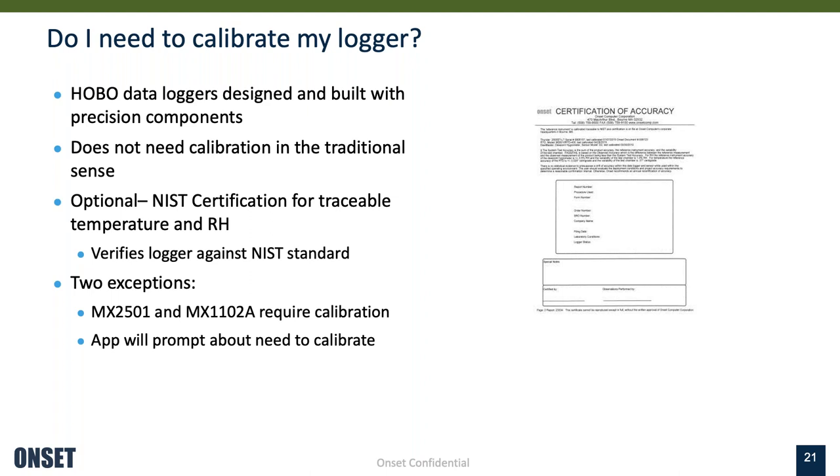And there's two processes there. One is a manual calibration where you would configure that device, and during that process, you're going to go through the actual calibration. And we recommend in that case, with the CO2 logger, you do that outside, right? So you want to get to a position where you're at the lowest CO2 that you can be for that calibration. Then there's also an AutoCal setting that you can run, and I believe it's every week or every 8 days it goes through this AutoCal process where it will do a little bit of math and auto-calibrate at that time period.